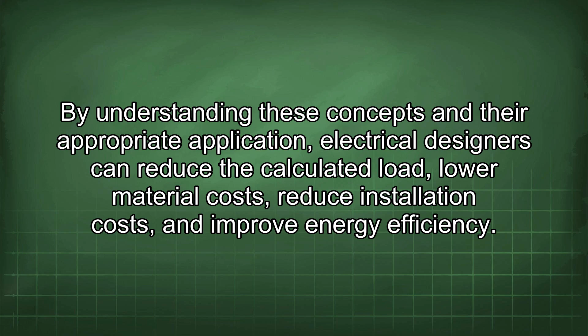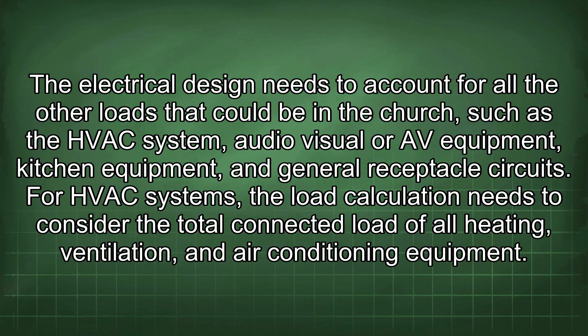The electrical design needs to account for all the other loads that could be in the church, such as the HVAC system, audio-visual or AV equipment, kitchen equipment, and general receptacle circuits. For HVAC systems, the load calculation needs to consider the total connected load of all heating, ventilation, and air conditioning equipment. This includes the compressors, fans, pumps, and any electric heaters. Demand factors can be applied to HVAC loads, but the specific demand factor depends on the type of HVAC system and the climate zone.